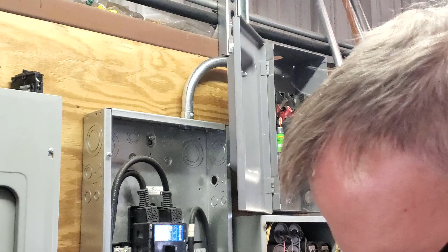I tried to take advantage of as many holes that were already in the boxes, but I did have to punch a new hole for the supply and then drill one into the main box. That's a pre-bent conduit elbow there. Working with the number 2 copper, that's about all I can do. Both my wrists, I've got some arthritis going on in there, and just getting that stuff to bend and conform is a little bit of a struggle. I don't know how the electricians do it with some of that monster in-feed cable they have.